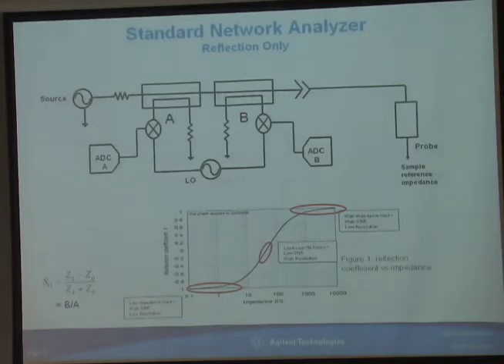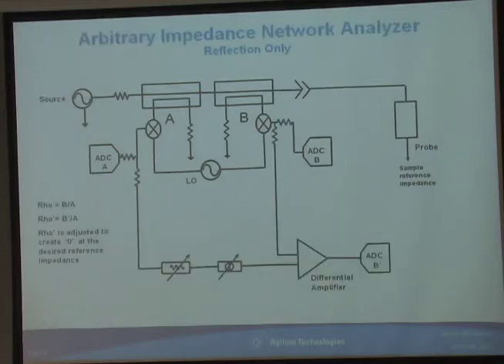So I showed you this picture before. Not much to say about it except high sensitivity, low sensitivity, and most nano devices are up here in impedance, so that's a problem. But we came up with a technique which allows you to recenter the high sensitivity region of the network analyzer. Basically what we're doing is building an interferometer, or a reflection canceller.